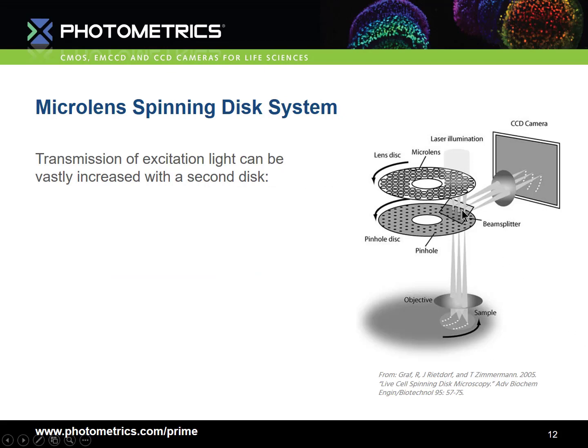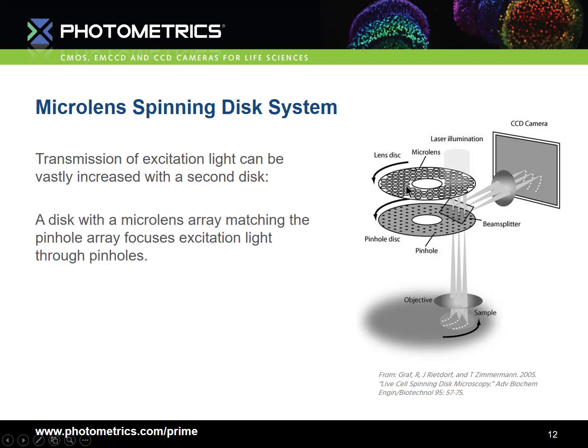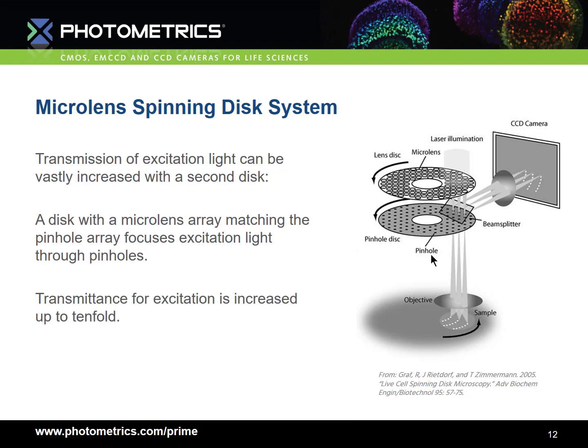One means of significantly improving the transmission of excitation light through the pinhole disk is to use a second disk. This disk contains a microlens array corresponding to the pinhole array on the first disk. These microlenses focus the excitation beam through the pinholes of the pinhole disk. Transmission for excitation light is therefore increased up to tenfold, however this has no influence on the amount of emission light detected.